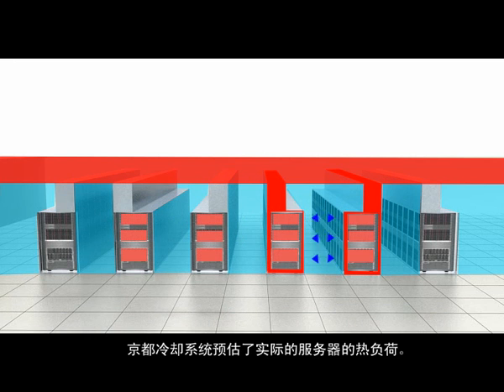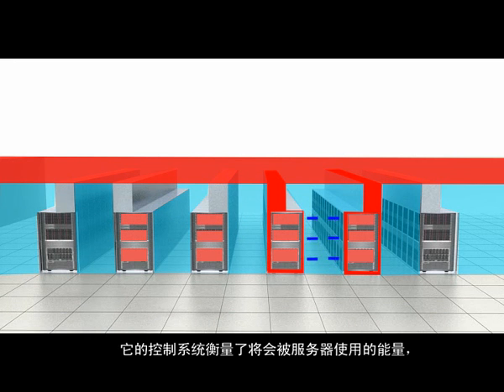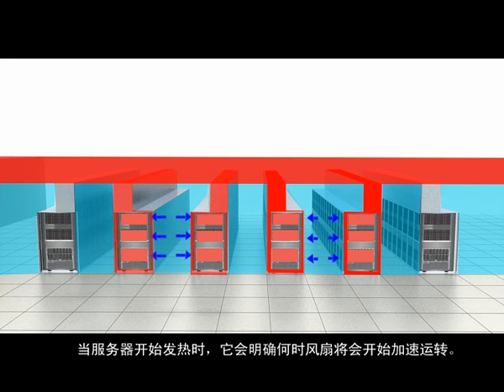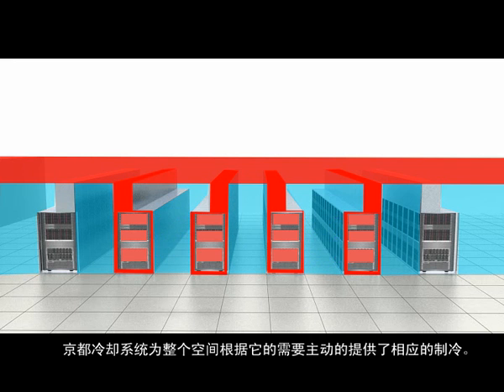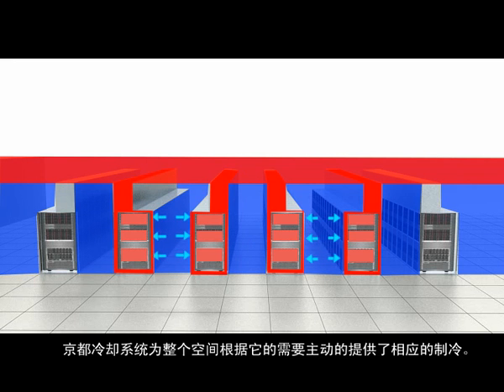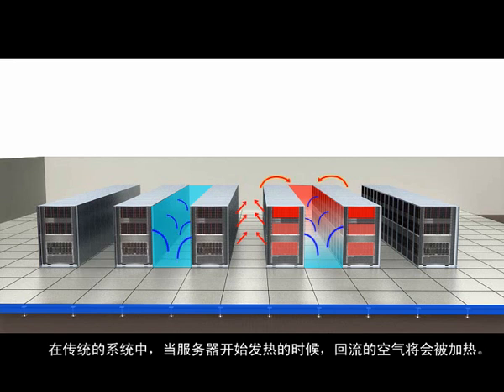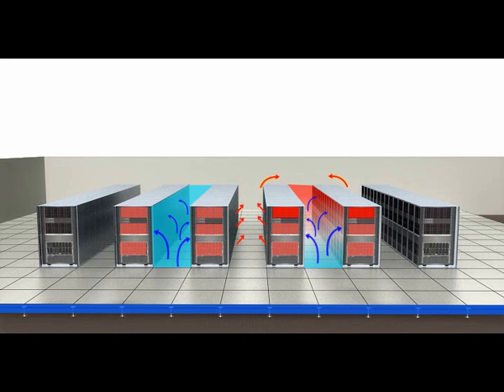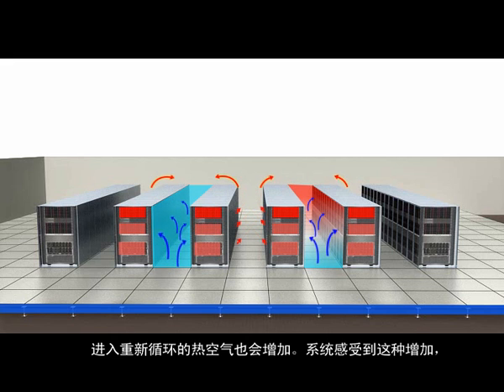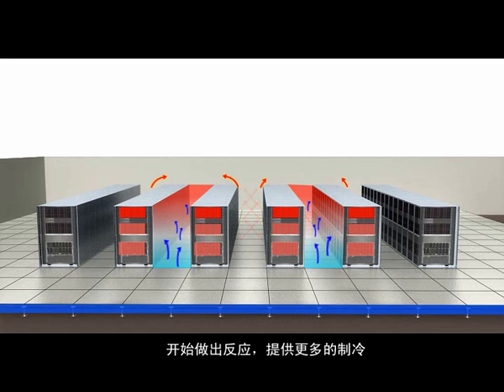KyotoCooling anticipates server heat load. Its control system measures the power going to the servers and knows when the server fans are ramping up and when the servers begin to generate heat. The KyotoCooling system supplies more cooling to the data hall proactively as it is needed. In traditional systems, the servers begin to generate heat, which warms up the return air. Recirculation of hot air increases. The system senses this increase and reacts by adding more cooling.